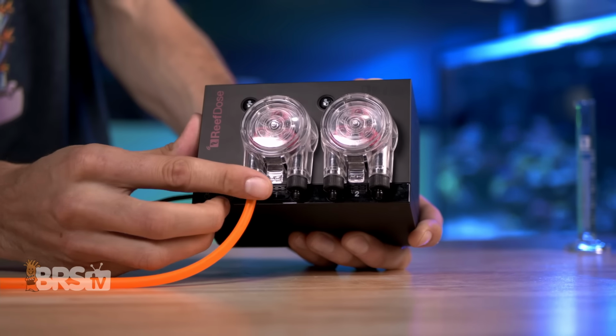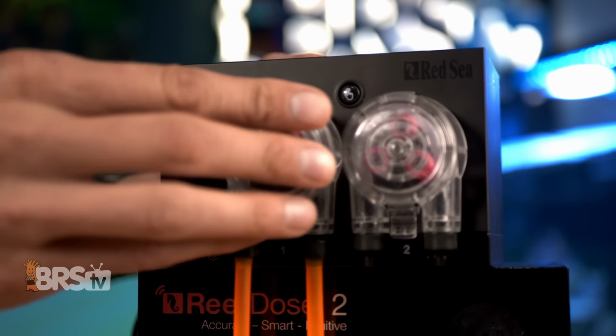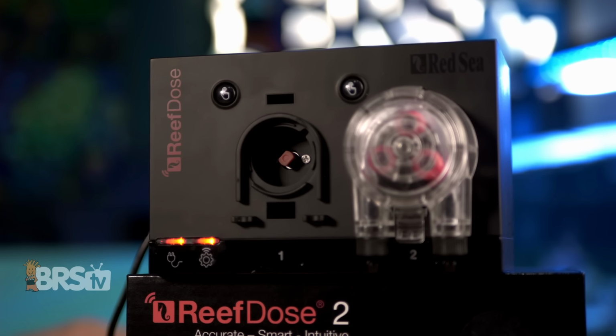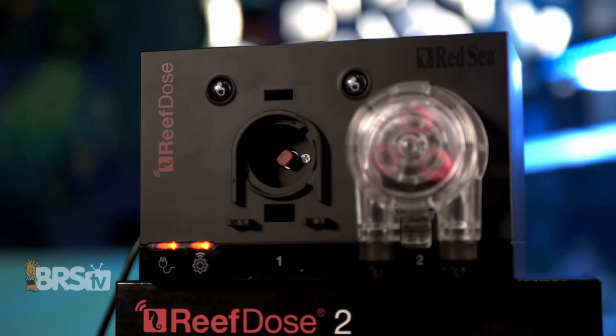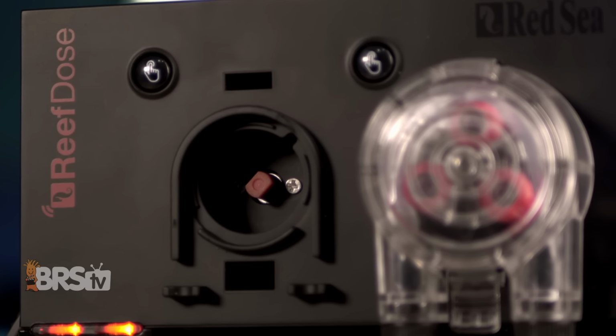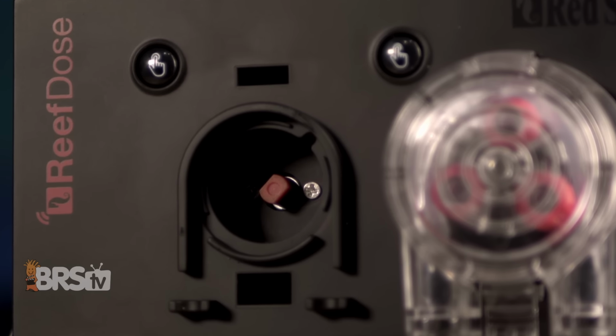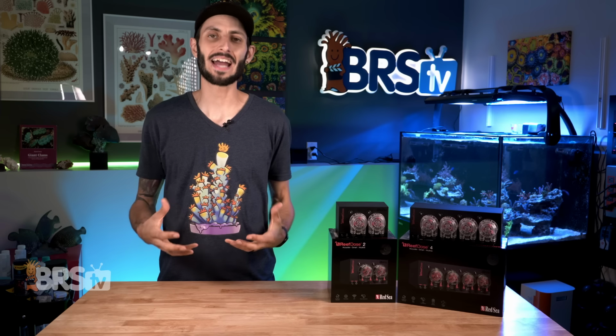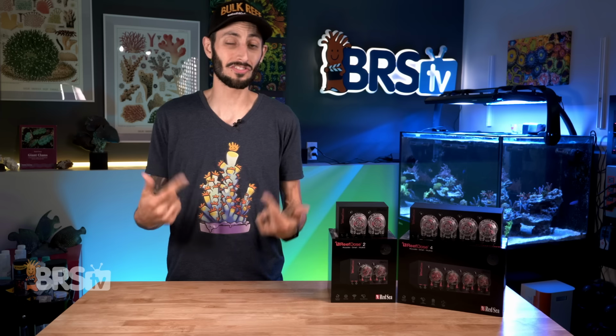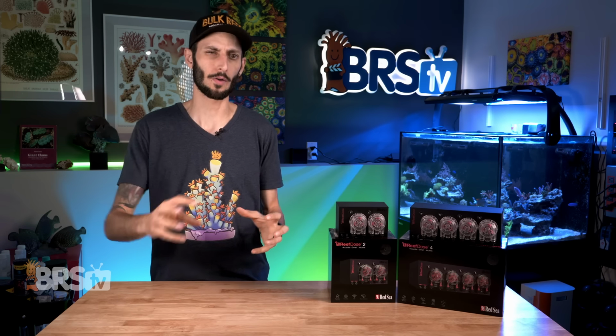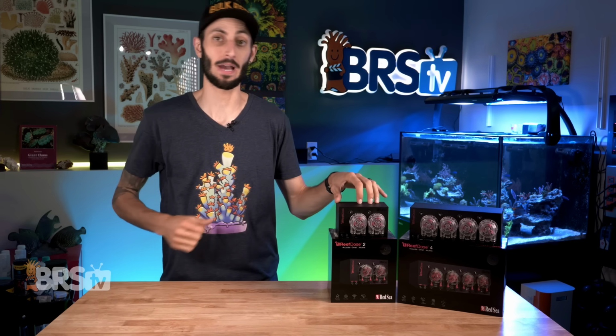When you flip them over, you'll notice the shaft that turns the dosing head isn't the typical cylindrical metal rod, but actually a rectangular peg, which prevents any slipping between the motor and the head, which plays a part in the accuracy of these dosers. They also automatically align and engage when the motors start up, so you don't need to stress over them being aligned perfectly when you snap the head back into place.